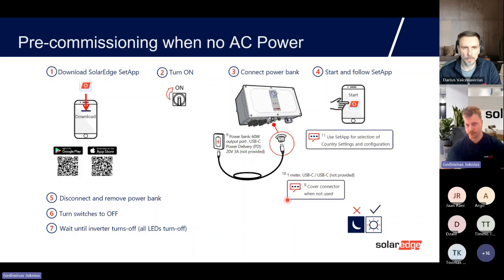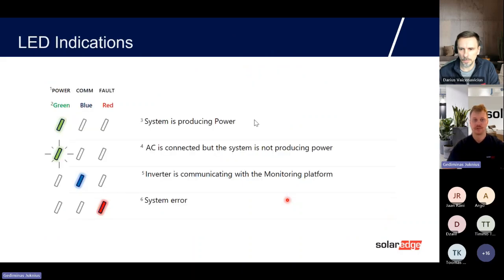If you do not do this before you get AC, once the grid operator gives you AC, you're going back to the site and then you do the commissioning on the DC. So you can really prepare the DC at a much earlier phase, and you don't need to waste time. You don't need to go to the site twice. I think it's a great thing. If anyone has any sites where you're planning to do the installation before you even get the AC connection, again, give us a message. We'll help you with any information needed.